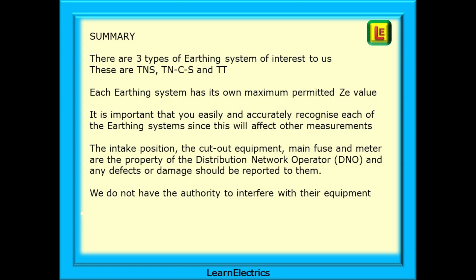A quick look back then. There are three types of earthing systems of interest to us. These are TNS, TNCS and TT. Each earthing system has its own maximum permitted ZE value and ZE is a measurement of the outside world. It is important that you easily and accurately recognise each of the earthing systems since this will affect other measurements. The intake position, the cutout equipment, main fuse and metre are the property of the distribution network operator or DNO and any defects or damage should be reported to them. We do not have the authority to interfere with their equipment. And that was a brief overview of how ZE is affected by different types of earthing systems.